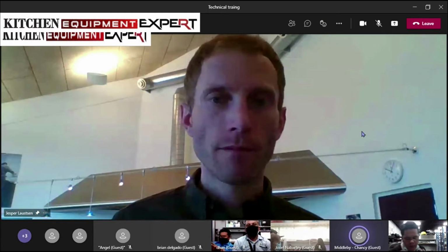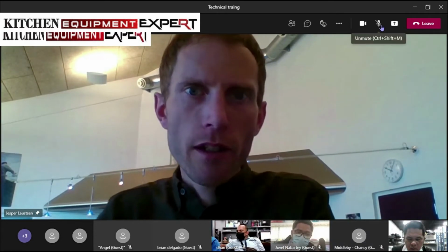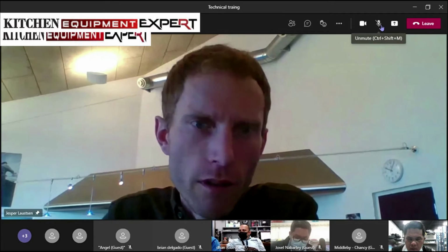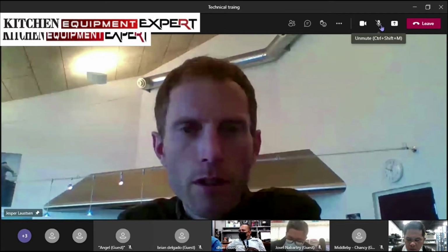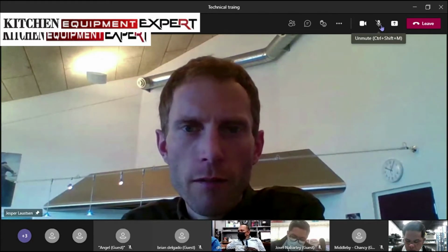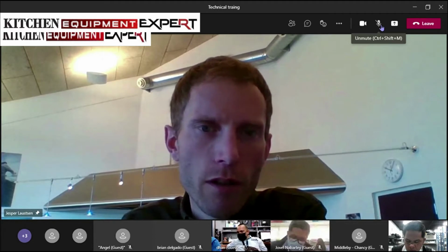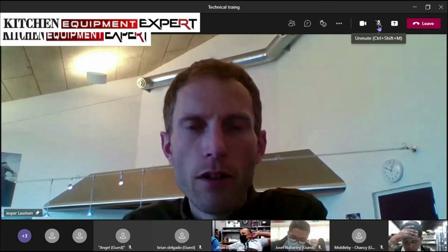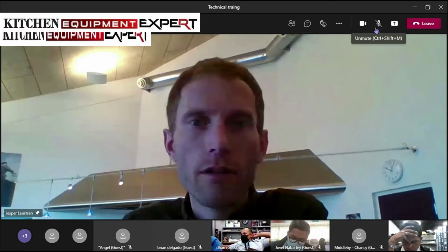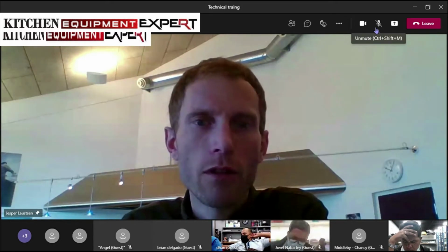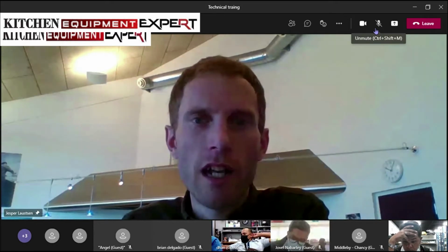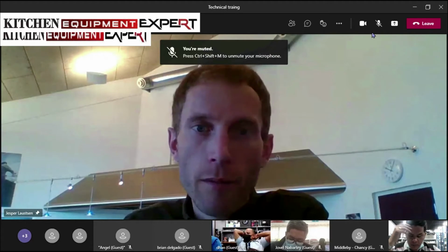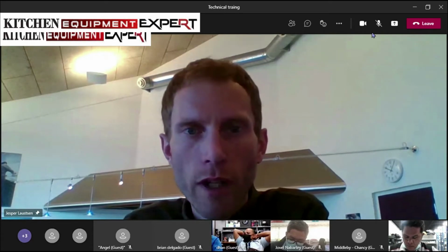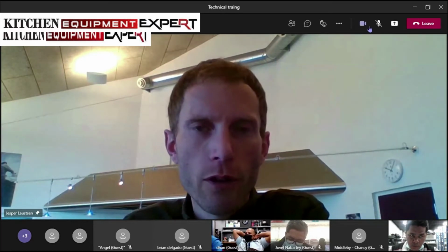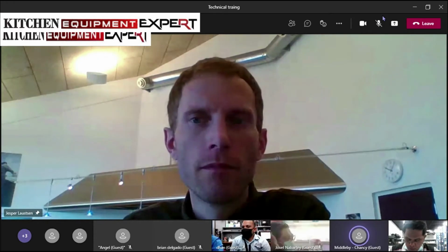What could be that error code? That could be error code 55, because if there's no oxygen in the system it cannot ignite, or there's no flame, so the startup system cannot start. Error 55. Or it can be 57 as well. Stop during operation. You mean, what if it's not temporary?